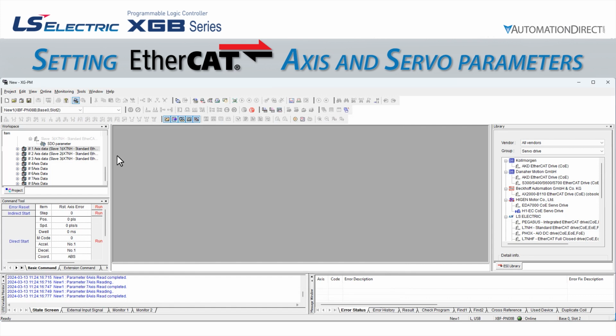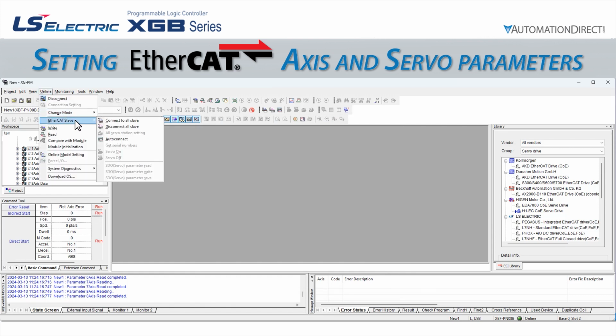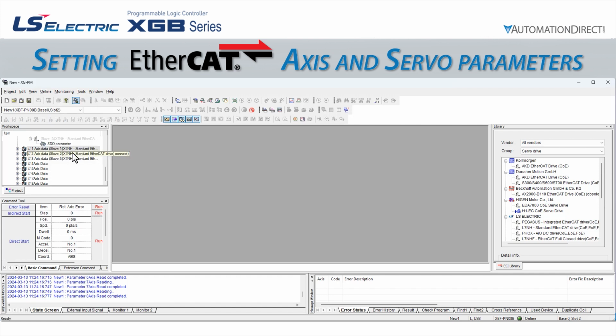The servo parameters are actually stored in an SDO file that gets written directly to the drive. If we were to remap which axis went with which drive, the servo parameters would follow the drive node number, not the axis number. Let's start by looking at the axis parameters.